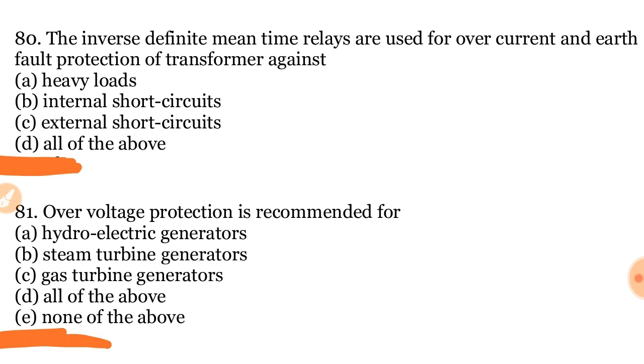80 question. The inverse definite mean time relay are used for overcurrent and earth fault protection of transformer against heavy load, internal short circuit, external short circuit, all of the above. Answer is internal short circuit. 81 question. Over voltage protection is recommended for hydroelectric generators, steam turbine generators, gas turbine generator, all of the above, none of the above. Answer is all of the above.